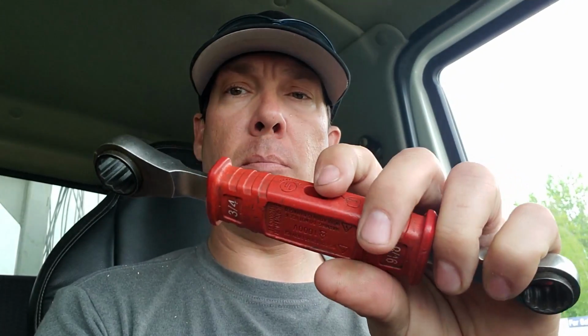You can see this one actually has a hole in it, and on the top and bottom of that, there's no metal in the center of this. If I were to put an ohm meter across, I'm not going to have continuity between the two metal ends. So with this guy, if you did hit a dead short on this end, while this end was on something live, you would be protected. To have plastic wrapped around the entire end is pretty redundant because you're on something that's live. Anyways, there are some manufacturers that do have some of the tools fully encased in plastic, however.